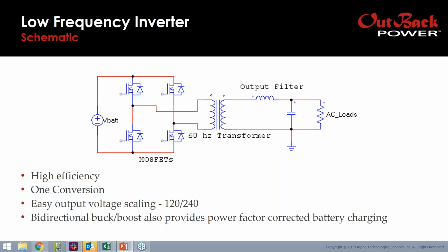This is a really brief schematic of a low frequency inverter, showing that the reason it's a fairly efficient inverter is that it has a single conversion. So directly from DC on the left, the MOSFET switches are switched in an alternating pattern that allows a direct conversion from DC to AC, or AC to DC, and that passes to the transformer through an output filter. It's easily scaled with the transformer. It's a 60 hertz transformer, easily scaled for output voltage, so 120 or 240 volts on the same winding. It's very easy to do.